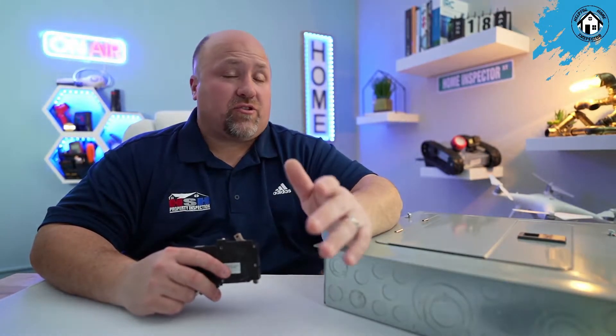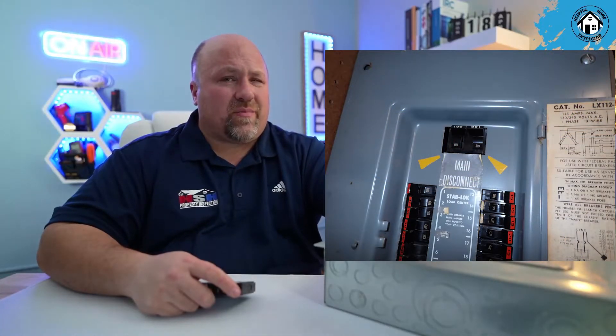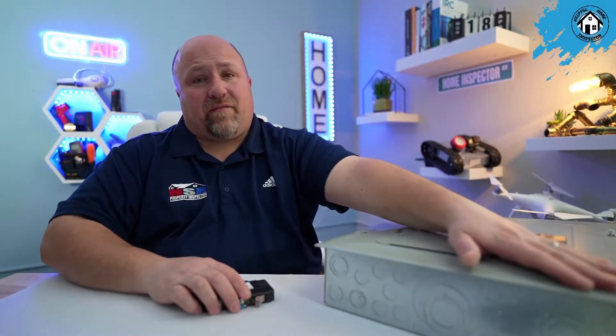Federal Pacific got their first patent in 1949, and in 1963 the Stab-Lok Breaker was patented. The Stab-Lok Breaker has been known to have all the issues — it had poor connection to the bus bar, they switched to different bus bar building materials, contact points were not connecting properly, and breakers were not tripping off at their suggested load. When a breaker doesn't trip at its designed rating, it can be overloaded and you run the risk of an electrical fire. The Stab-Lok was a UL-listed product.